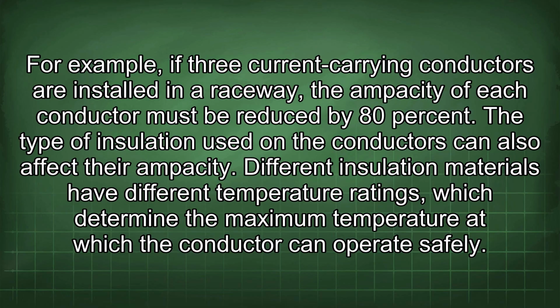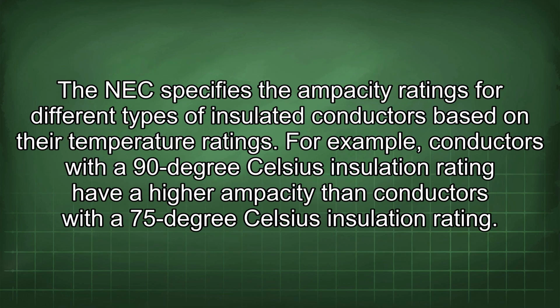Different insulation materials have different temperature ratings which determine the maximum temperature at which the conductor can operate safely. The NEC specifies the ampacity ratings for different types of insulated conductors based on their temperature ratings. For example, conductors with a 90°C insulation rating have a higher ampacity than conductors with a 75°C insulation rating.